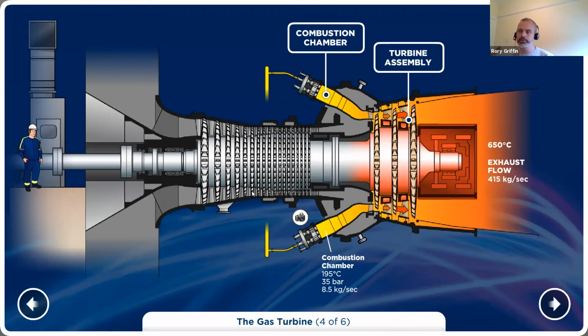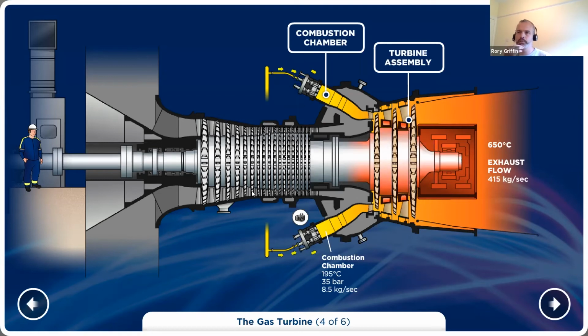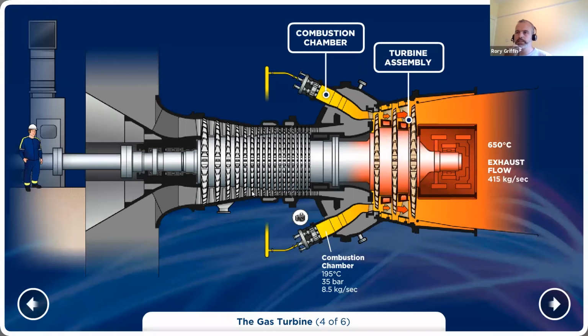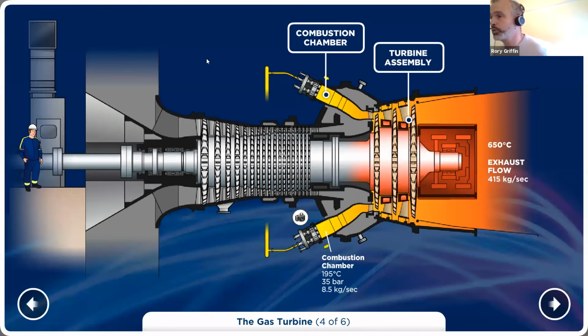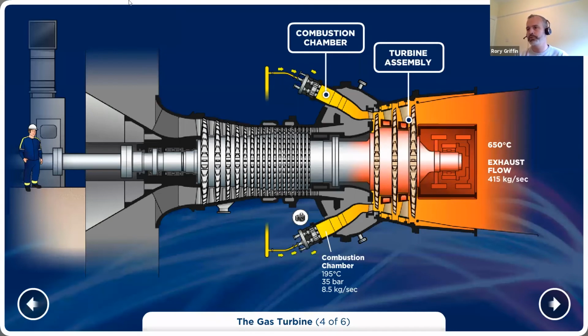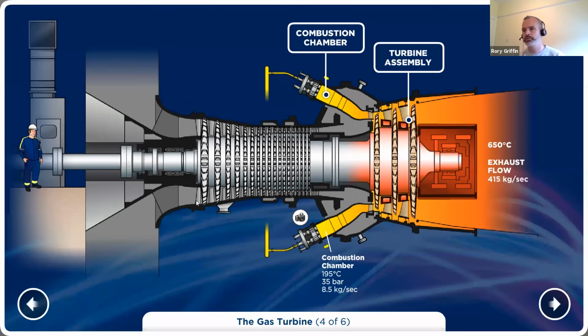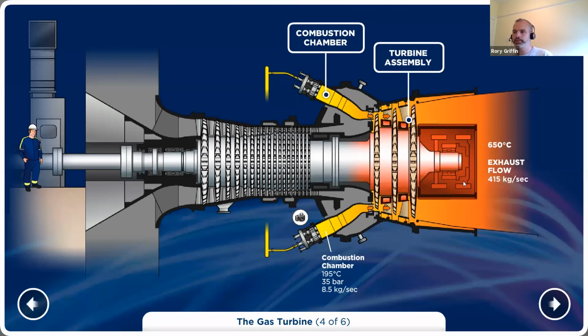And I suppose this tool is also used for the grid to send instructions down, be it for energy actions like megawatts up and down the range, or maybe to provide voltage support in the area through megavar instructions. So quite a dramatic drop. And on the exhaust flow itself, it's at 650 degrees. The flow rate, so you've had 2,200 tons per hour coming in on the air, added with a bit of gas. So you're up around 2,250, 2,300 tons. And the other thing to bear in mind, this is swirling at 3,000 RPM. So there's quite a lot of energy still in the exhaust of the machine.